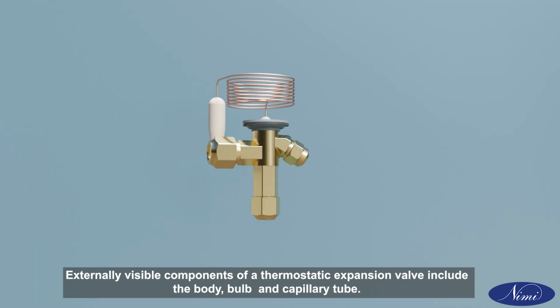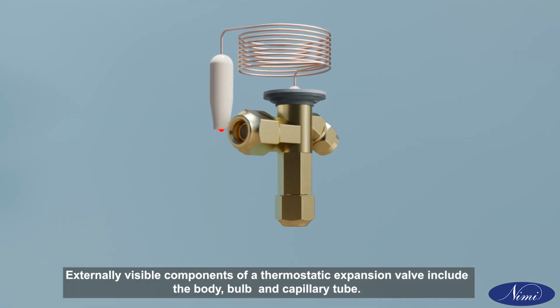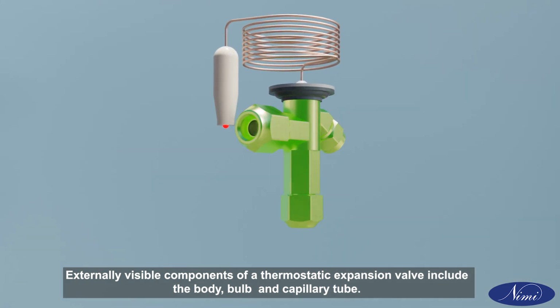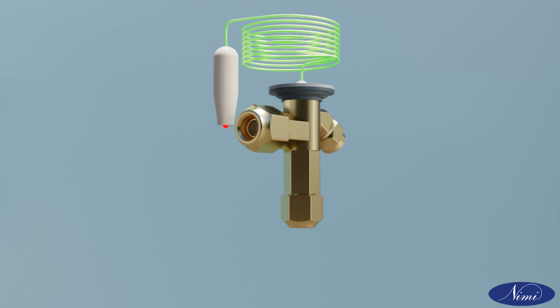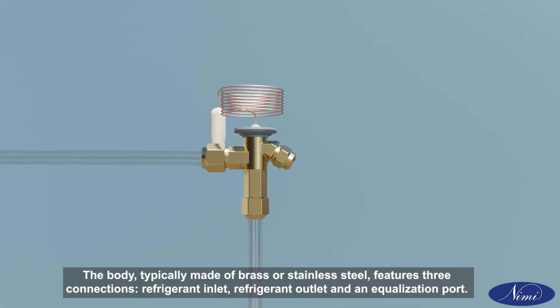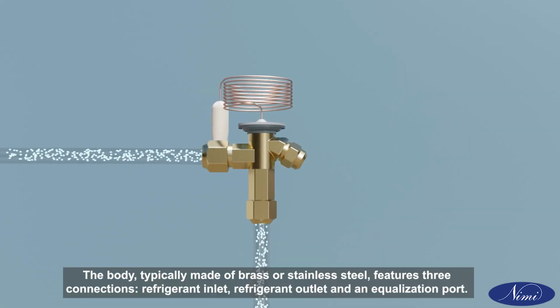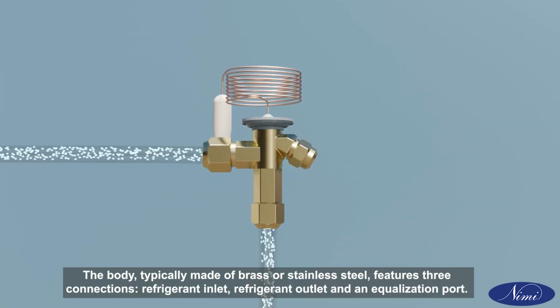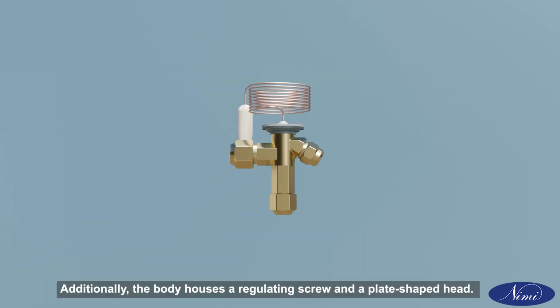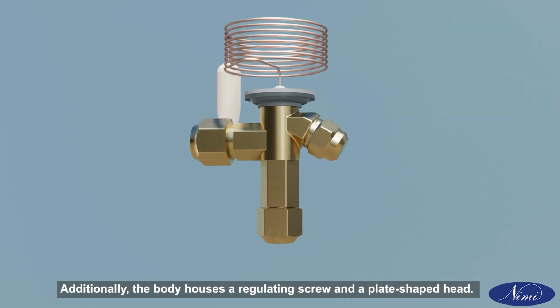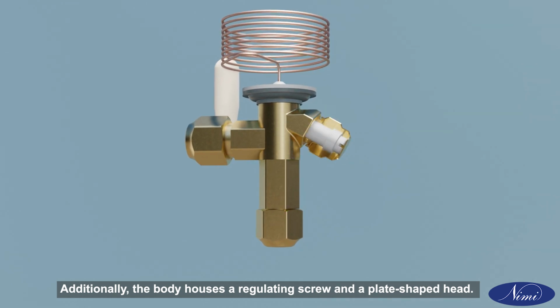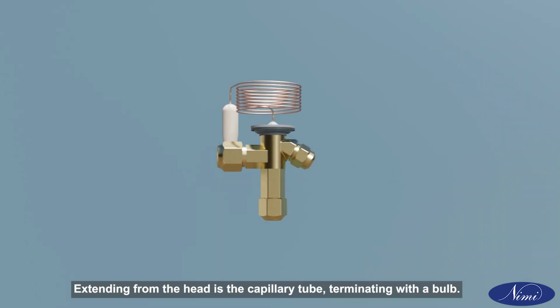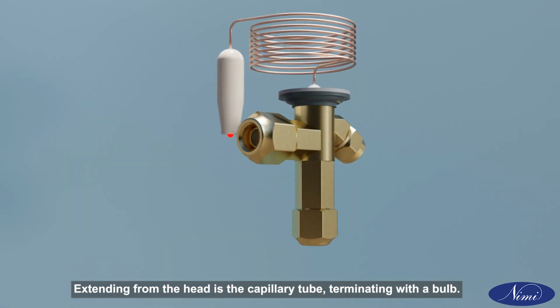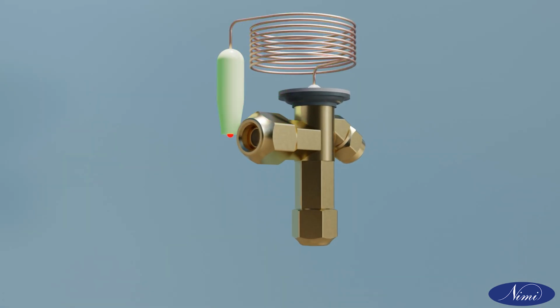Externally visible components of a thermostatic expansion valve include the body, bulb, and capillary tube. The body, typically made of brass or stainless steel, features 3 connections: refrigerant inlet, refrigerant outlet, and an equalization port. Additionally, the body houses a regulating screw and a plate-shaped head. Extending from the head is the capillary tube, terminating with a bulb.